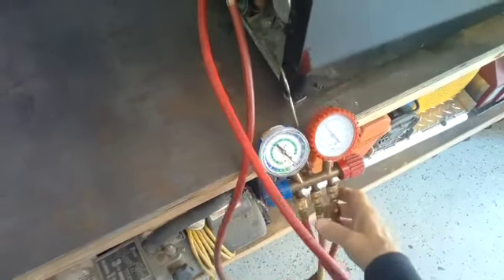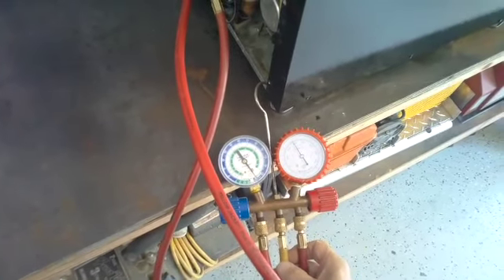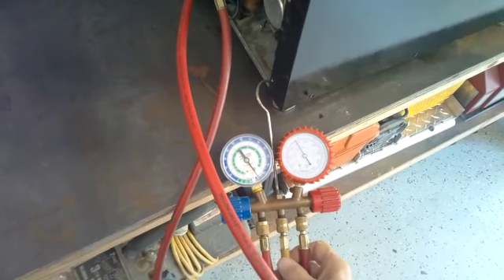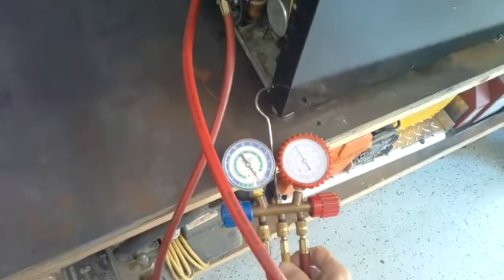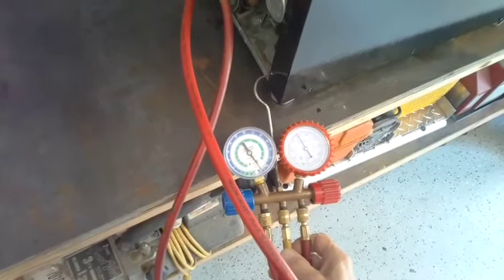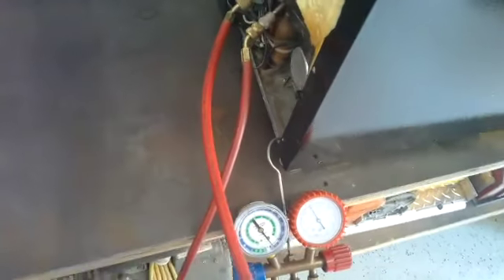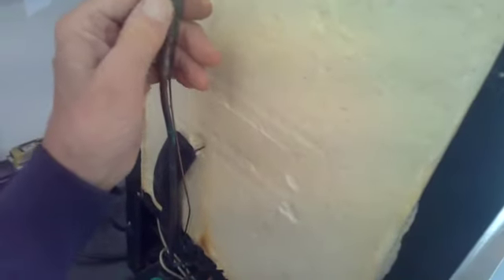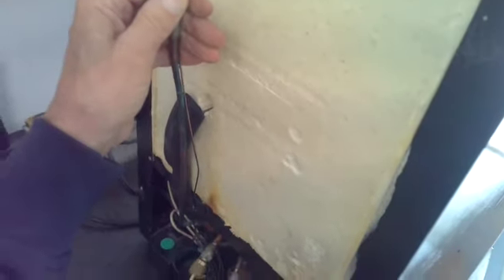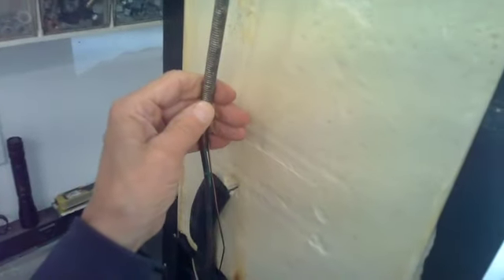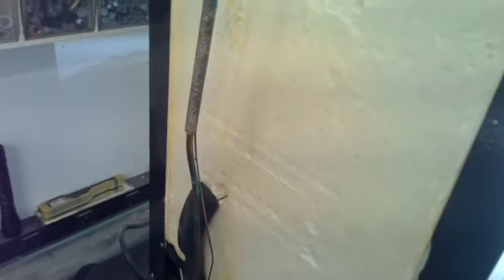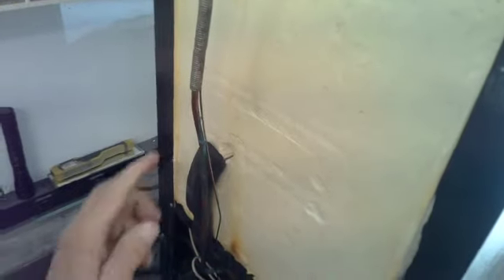Okay, now we're going to leave this nitrogen in the system for a while and see if the pressure drops, just to confirm that we have a leak. Now we did possibly find a leak in here. I was picking something up in this. I call this a heat exchanger, but according to the parts manual, it's called suction line service. So we found a part number. We're checking with the factory to see if these things are still available.